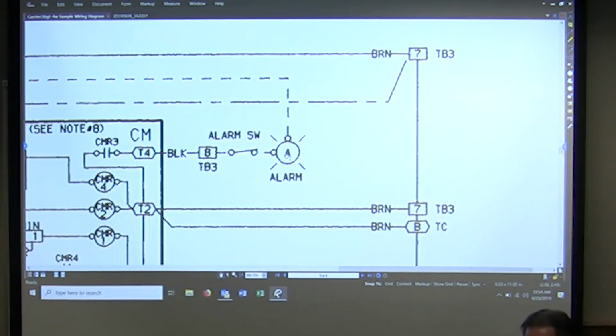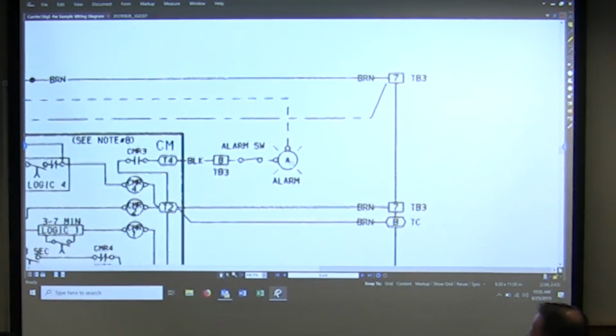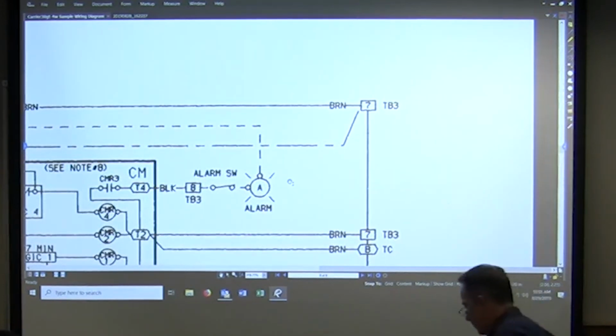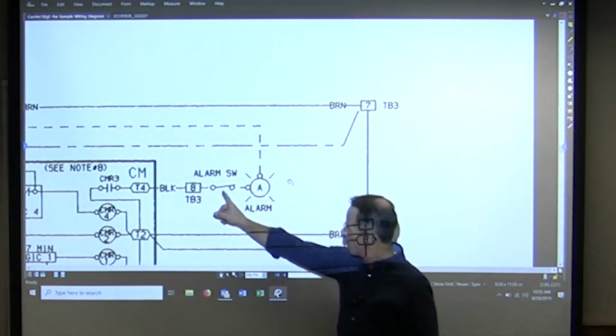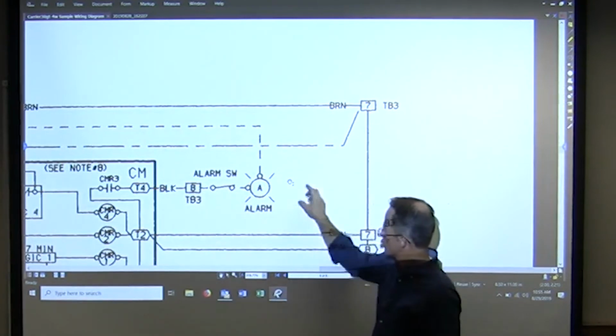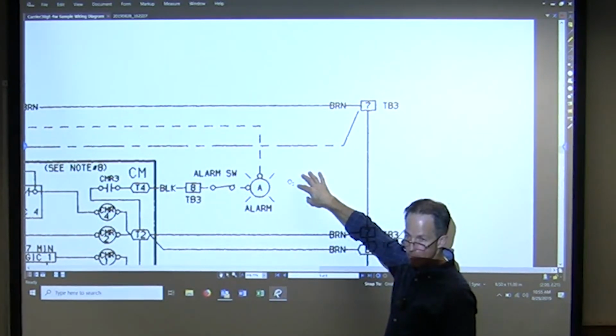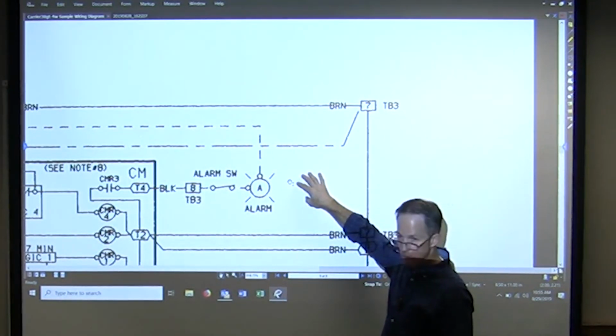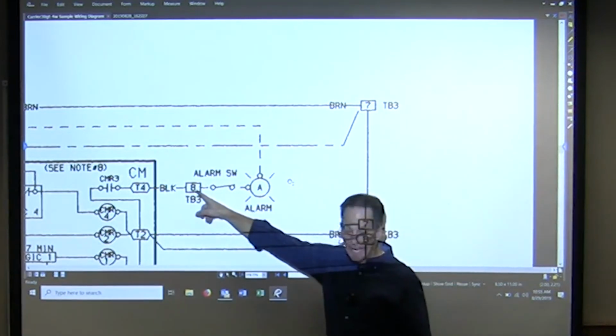How would you monitor this with the building automation system? You just go switch coming off that alarm switch, drop down there, put in whatever you need to do, and bring it back. Status relay. Yeah, you can status 24 volt relays. What I could do here is come off of here over to a relay coil? No, you want to go from off terminal 8. Yeah, probably 8, right?